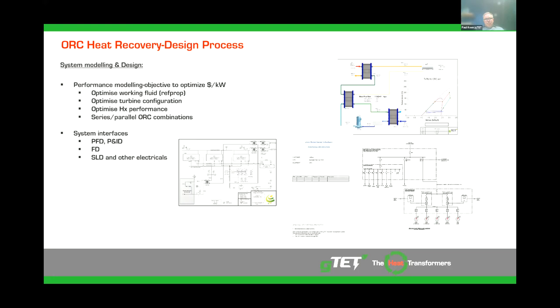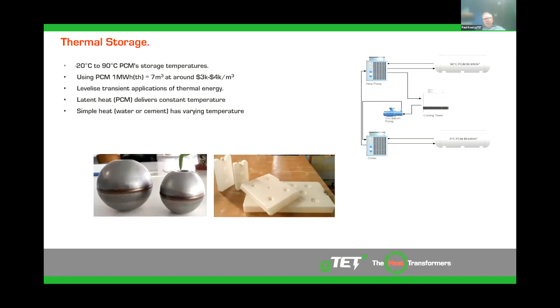System interface will be detailed with process flow, pipe instrumentation diagrams, functional descriptions, single line diagrams. As I mentioned before, thermal storage is a key to enabling intermittent and variable waste thermal energy to be available when needed by load shifting to match demand. Phase change materials selected to match the application enable the heat to be released at a constant temperature. GTET can provide PCM storage from minus 20 degrees Celsius up to 90 degrees with 130 degrees Celsius currently in development. The high energy density associated with these phase change materials typically delivers a megawatt hour of thermal storage capacity in a 7 cubic meter vessel. Lower cost sensible heat storage solutions, including insulated water tanks or cementitious materials, can also be used where the process doesn't require a constant temperature.